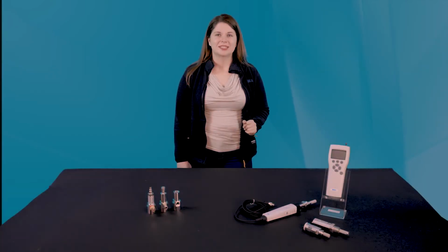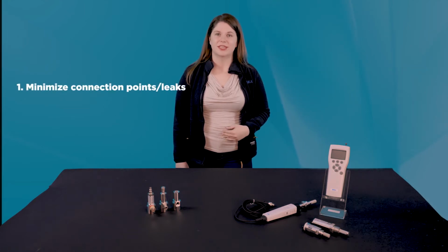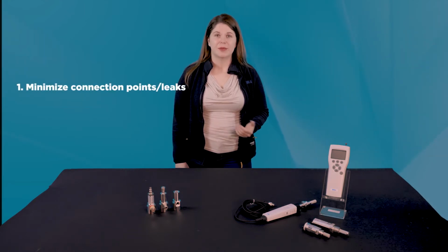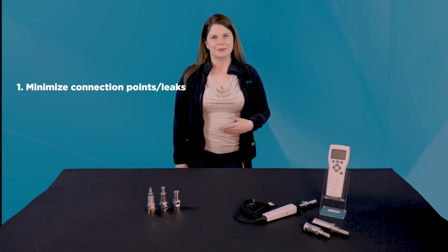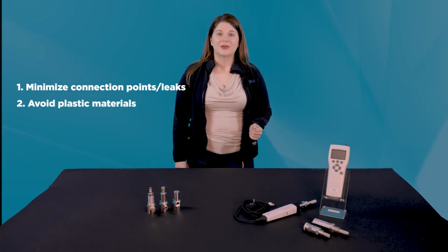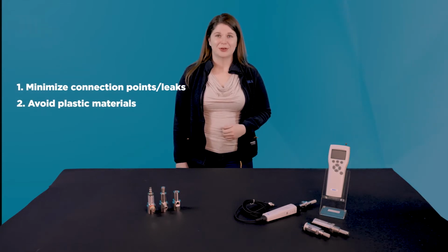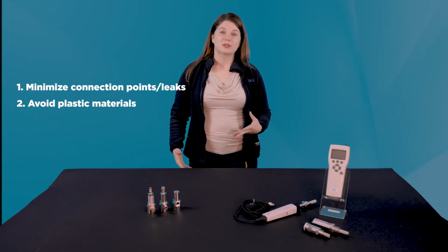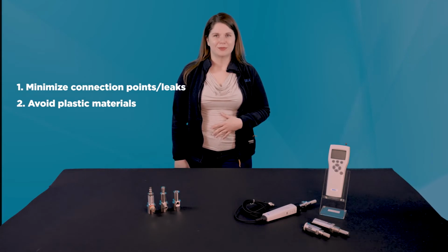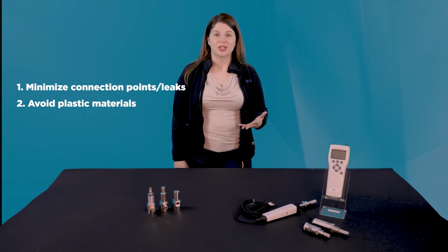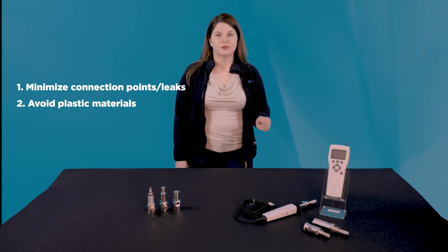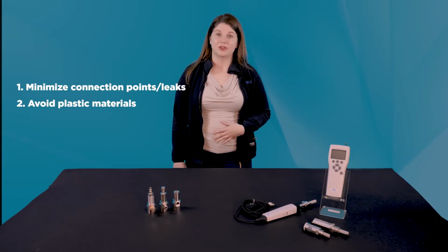First, minimize connection points to reduce risk of leaks. You don't want moisture from outside the process leaking in. 2, no plastic or rubber tubing. Stick to high-quality metallic materials for connections and sealing, since most plastics will absorb water vapor. Teflon is an exception, which is acceptable for use for dew points down to -40 degrees.